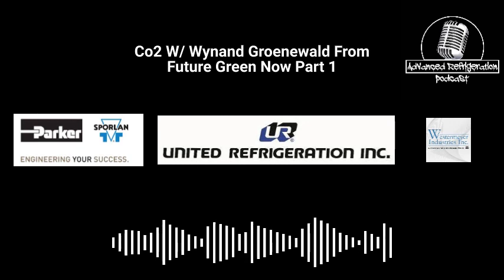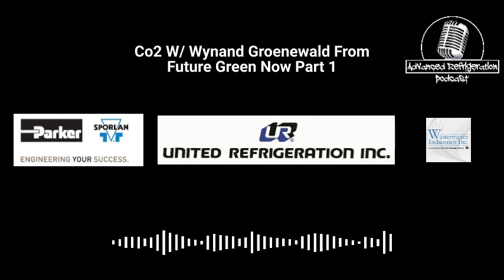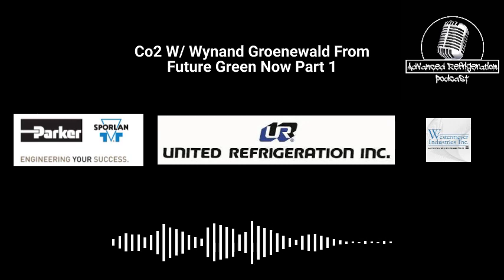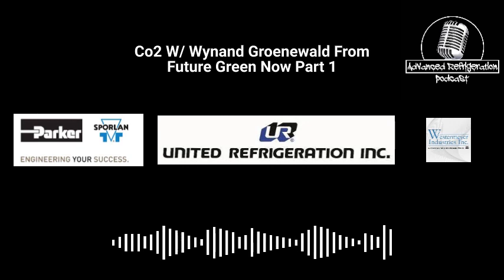I have a question now that you brought up the blast freezers. I did a little bit of industrial for a couple of years, and most of the stuff was blast freezers filled with liquid. You had a vessel at the top fed off the pump liquid, and that receiver at the top would fill up based off of a Hansen rod, so it's trying to maintain that level in there. Typically you have a hand expansion valve. Is that the same? Are you doing a lot of the same stuff with industrial liquid flooded evaporators with CO2 as you would with ammonia? I think a little bit less mechanically and more electronically, but similar concepts. Yeah, I would say similar concepts.